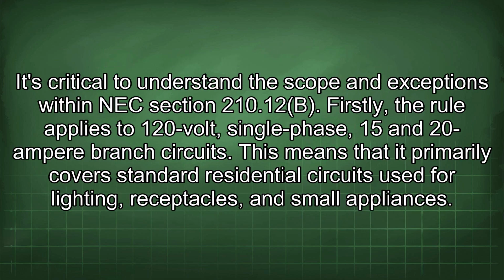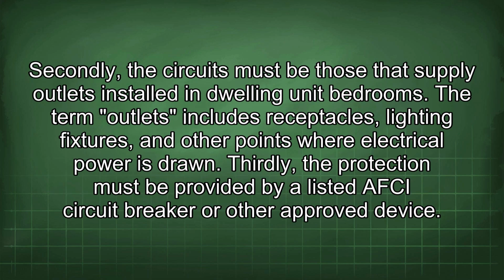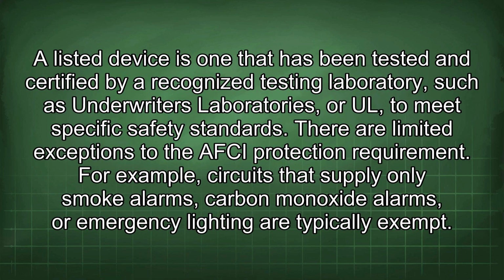It's critical to understand the scope and exceptions within NEC Section 210.12(B). Firstly, the rule applies to 120-volt single-phase 15 and 20-ampere branch circuits. This means that it primarily covers standard residential circuits used for lighting, receptacles, and small appliances. Secondly, circuits must be those that supply outlets installed in dwelling unit bedrooms. The term outlets includes receptacles, lighting fixtures, and other points where electrical power is drawn. Thirdly, the protection must be provided by a listed AFCI circuit breaker or other approved device. A listed device is one that has been tested and certified by a recognized testing laboratory, such as Underwriters Laboratories, or UL, to meet specific safety standards.